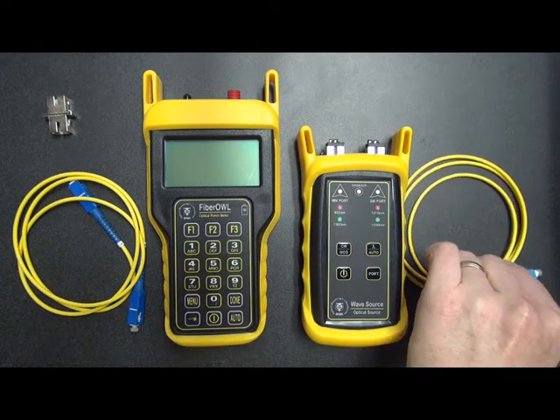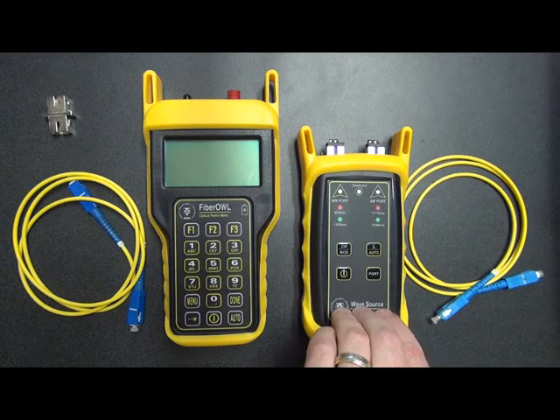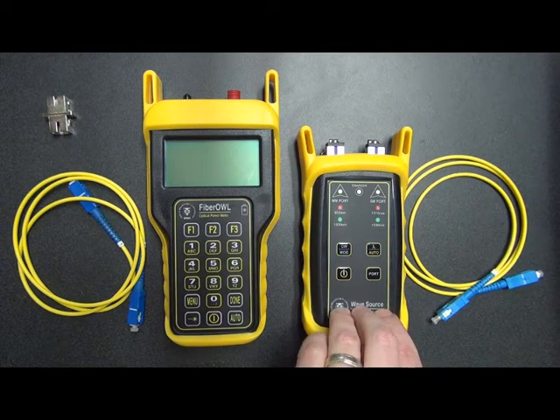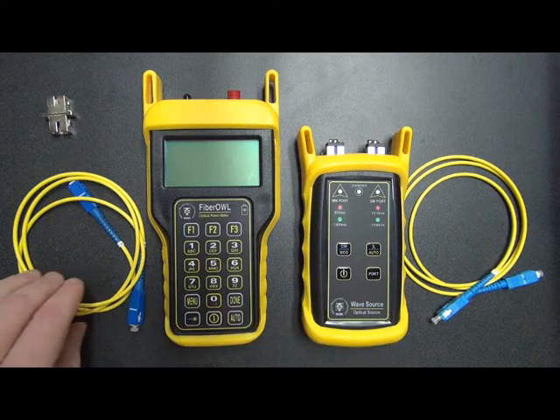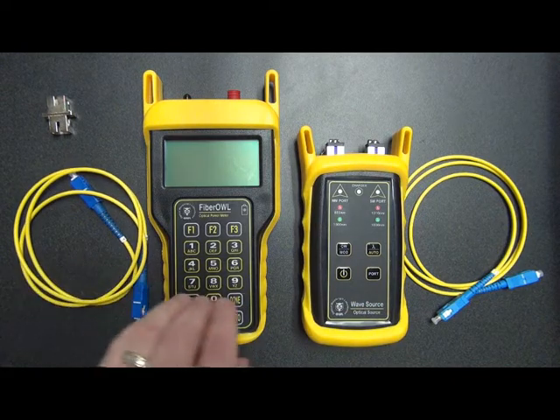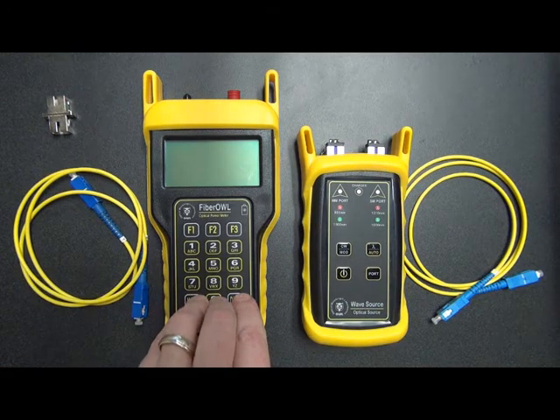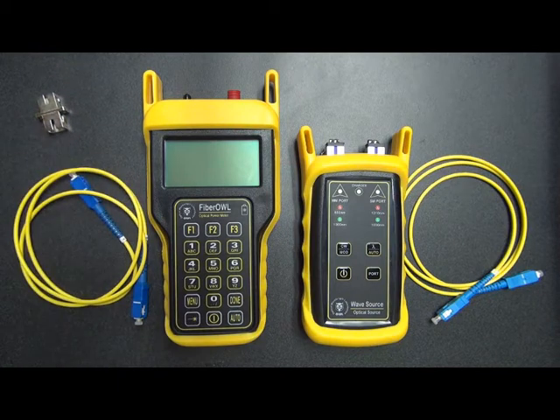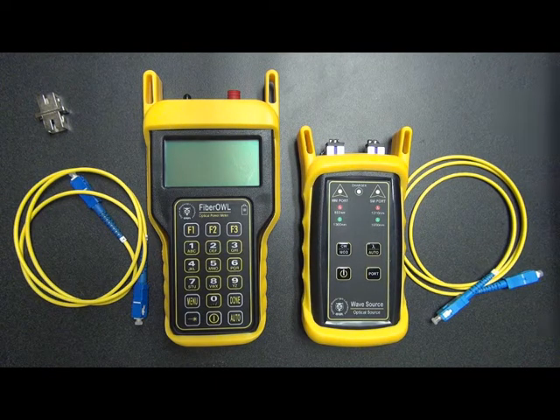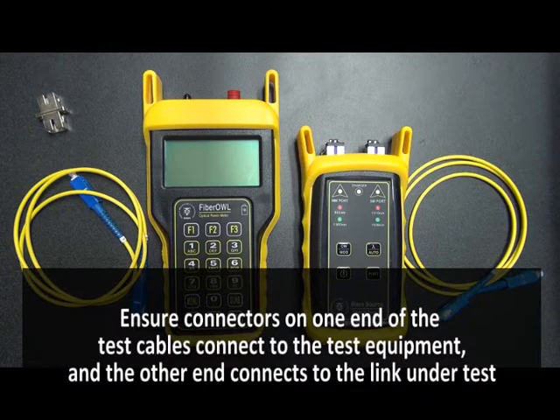This reference cable will be used to connect the WaveSource into the link under test and also zero out the equipment together. This patch cable will be used to connect the FiberOWL into the link under test, and the mating sleeve will be used to connect these two cables together for the purpose of checking them to make sure they're working fine.